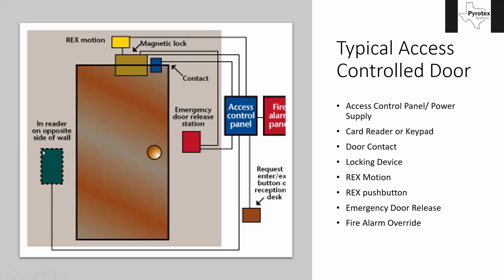The green element with the dotted line is installed on the outside of the controlled area — your keypad or card reader to let you in. The last element is the fire alarm panel, shown with a single contact point. Typically we don't wire directly to the fire alarm panel; we go to one of our addressable relays, which can be installed above the ceiling or in an IDF or MDF room, depending on the building's needs.